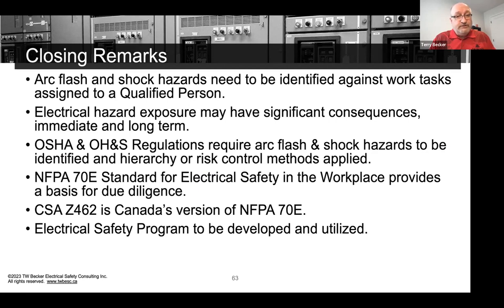So closing remarks. Electrical hazards need to be identified, but it's work task based, right? So it's about the work task first, then what's the maximum nominal voltage as I was indicating, and then is it high enough that I can get shocked or sustain an abnormal arcing fault? And then we use shock risk assessment and arc flash risk assessment procedures in 70E and Z462 to get the boundaries and determine when we need the PPE.